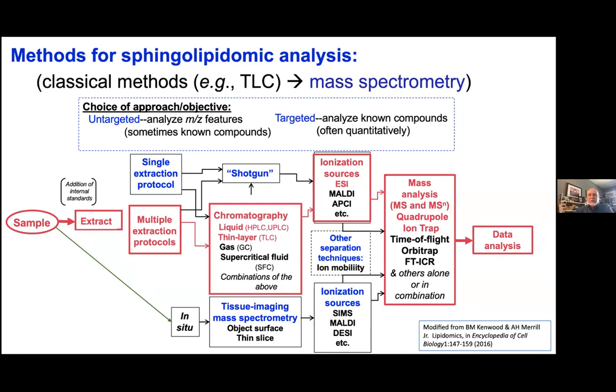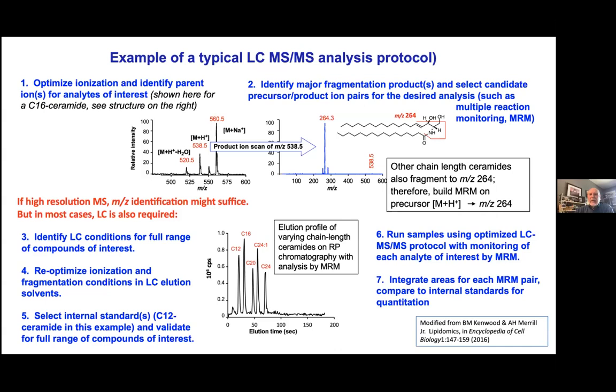I've given references to the different types of chromatographies. Now let's think more about the core mass spectrometry part. This is a flow sheet of what we typically do: for any category of sphingolipids of interest, look at optimized ionization conditions, the voltages on the instrument on all sides, temperature for the electrospray, and the voltage for ionization, which can be very important. For example, the shorter the chain on the ceramide, the lower the voltages you need — otherwise you'll get in-source fragmentation of the ceramides. The longer the chain, the higher the voltage needed to get them to ionize. So there's a lot of playing around with that, and when you have samples you often have to program the protocol to cycle through a series of steps to analyze the different chain-length species with different parameters for the multiple reaction monitoring.